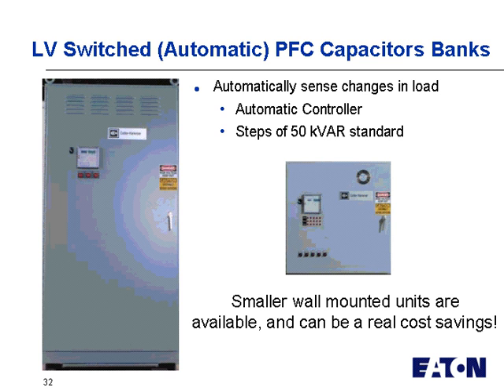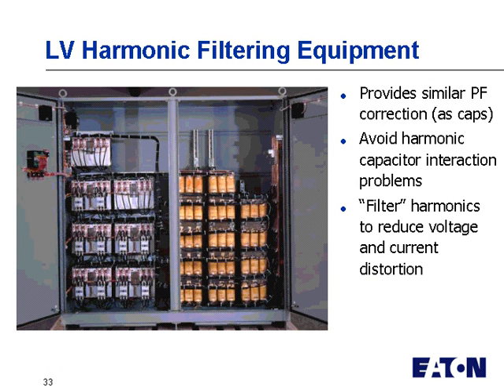Next, we have low voltage automatic or switched banks, and they could be, again, left is floor mounted for larger banks, or right is wall mounted for smaller banks. And these have a small controller in there that actually takes in and out steps of 50 kVAR, which controls the capacitors so that you don't cause that overvoltage issue, for example. And you can regulate around the actual power factor that's required.